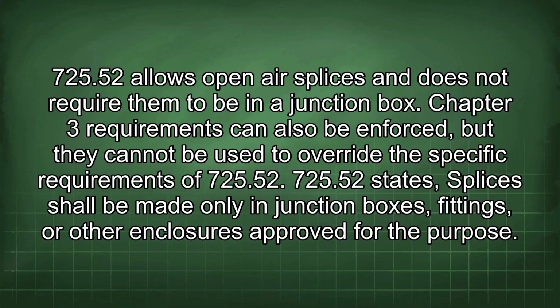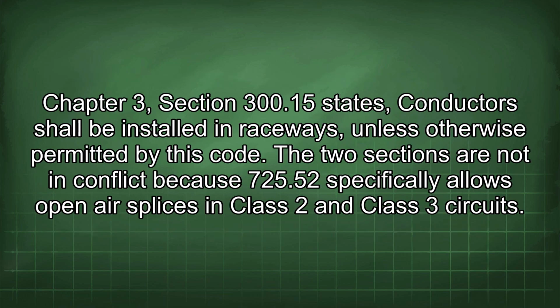725.52 allows open-air splices and does not require them to be in a junction box. Chapter 3 requirements can also be enforced, but they cannot be used to override the specific requirements of 725.52. 725.52 states, splices shall be made only in junction boxes, fittings, or other enclosures approved for the purpose. Chapter 3, Section 300.15 states, conductors shall be installed in raceways, unless otherwise permitted by this code.